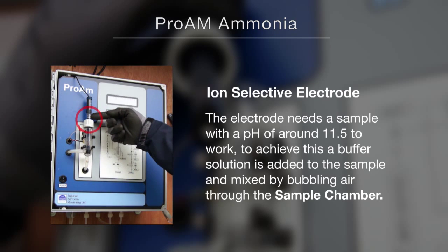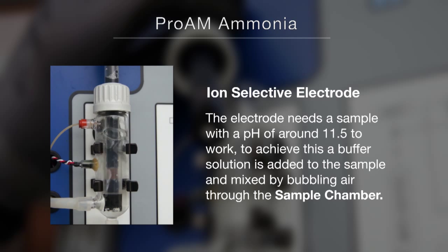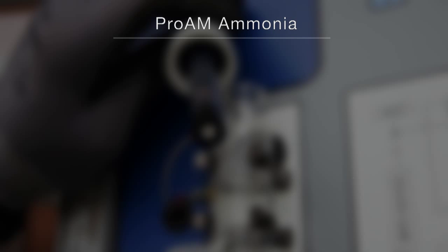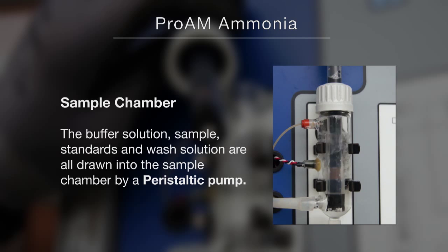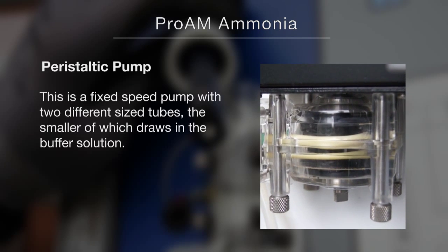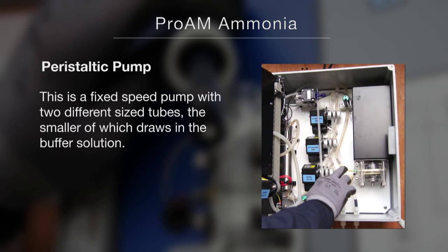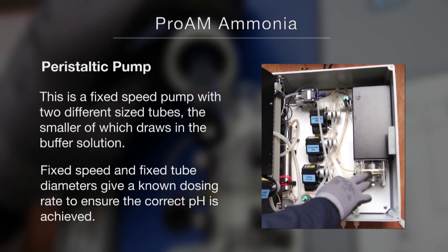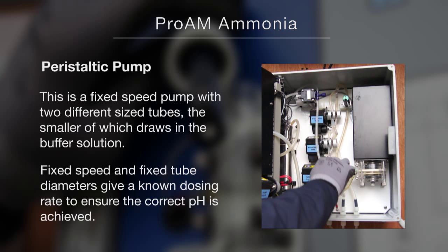In order for the ion selective electrode to work, the sample's pH needs to be elevated to around 11.5 pH. To achieve this, a buffer solution needs to be added to the sample and mixed by bubbling air through the sample chamber. The buffer solution, sample, standards and wash solution are all drawn into the sample chamber by a peristaltic pump. This is a fixed speed pump with two different sized tubes, the smaller of which draws in the buffer solution. The fixed speed and fixed tube diameters give a known dosing rate to ensure the correct pH is achieved.